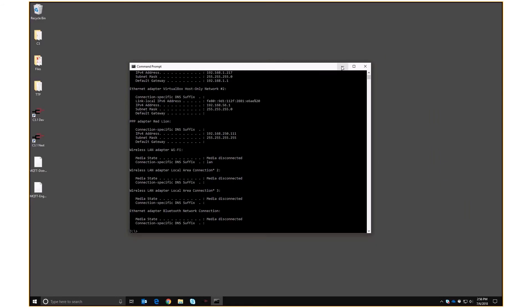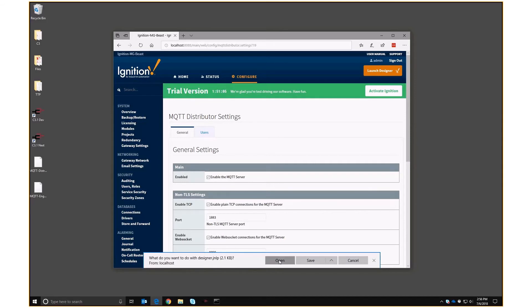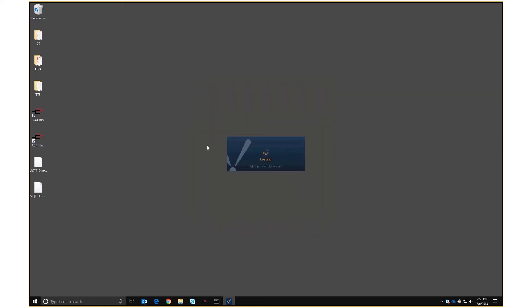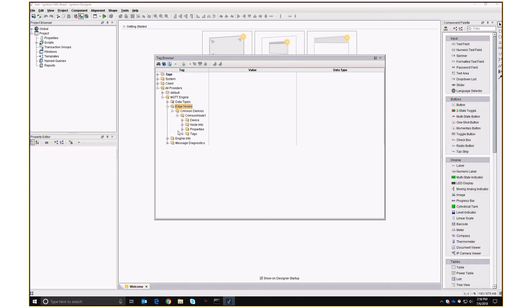Now let's go into Ignition and see if it's worked. We go back into the Ignition web client and click 'Launch Designer,' which runs a Java program that lets us see what's going on under the hood. We sign in with admin and password, create a new project called 'test,' and here we are. The interesting thing is the tag browser — under All Providers, MQTT Engine, Edge Nodes, we refresh and there we have Crimson Devices, Crimson Node One, Tags, and sure enough here are our tags, and you can see they're updating.